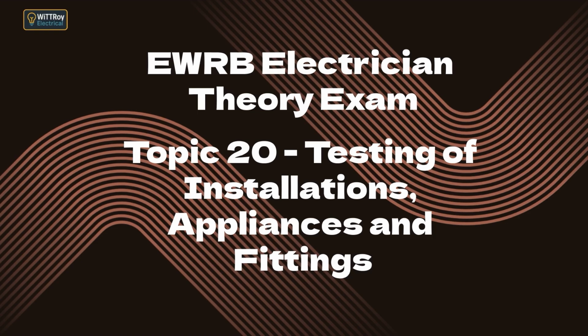This includes checking correct cable sizes, correct circuit protection, correct RCD placement, correct terminations, mechanical support for cables, correct identification, IP ratings of fittings, earthing continuity and bonding, and that equipment is undamaged and installed to standard. This step confirms that the installation meets the wiring rules and is ready for testing. A compliance certificate cannot be issued unless both the visual inspection and the tests meet the standard.